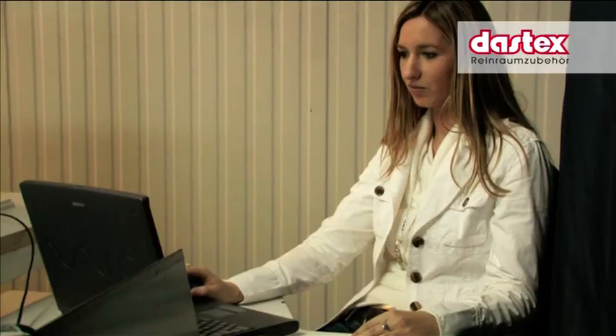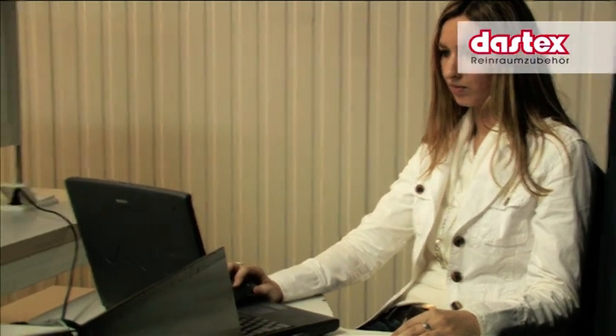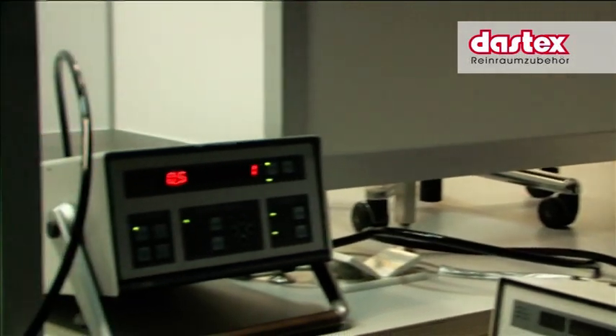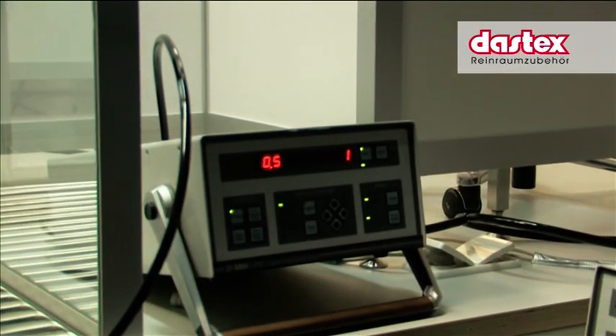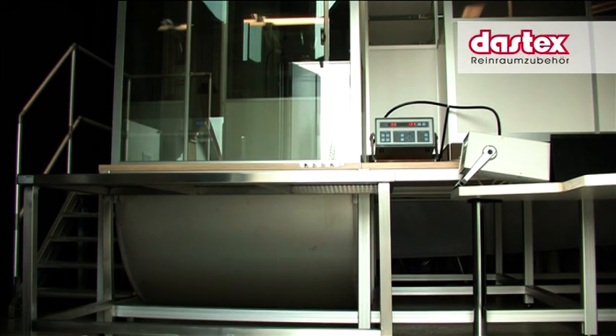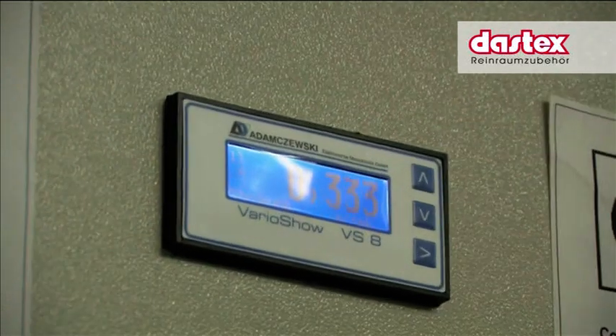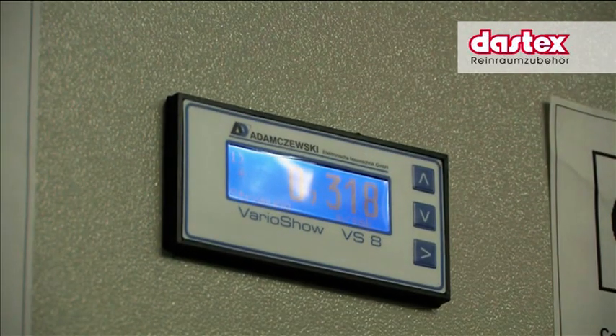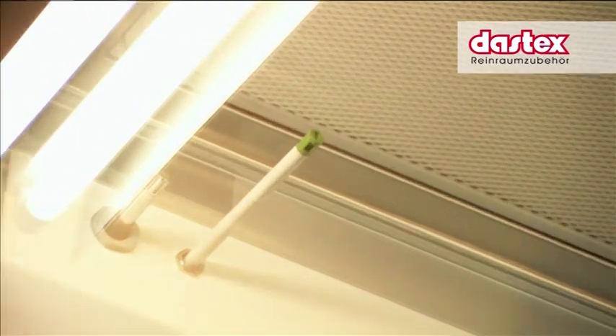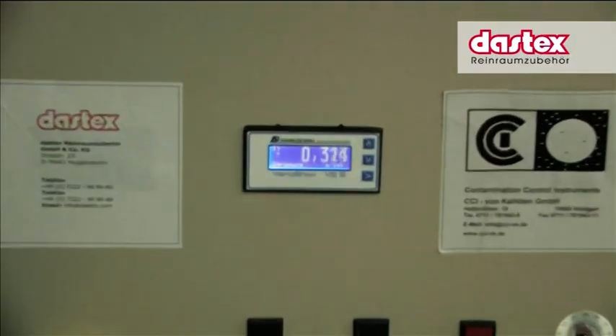How is an examination typically performed? To reach and maintain ISO-4 conditions within the body box, it is compulsory to run the filter and ventilation unit between 30 and 60 minutes prior to the intended measurements. In addition, the surrounding parameters like relative humidity — mostly 45% — and desired airspeed around 0.33 meters per second have to be determined in advance.